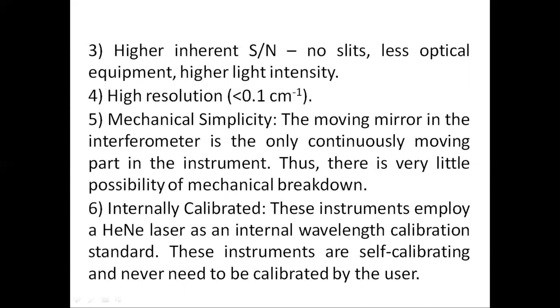So, Fourier transform infrared spectroscopy is preferred over dispersive or filter methods of infrared spectral analysis for several reasons. It is a non-destructive technique, it provides a precise measurement method which requires no external calibration, it can increase speed, collecting a scan every second, and it can increase sensitivity. One second scans can be co-added together to ratio out random noise. It has greater optical throughput. It is mechanically simple with only one moving part.